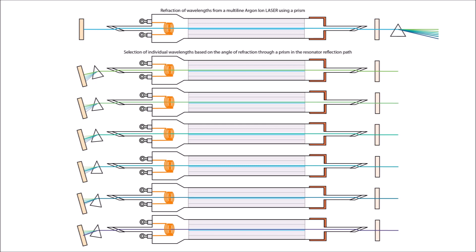Many argon ion lasers are multiline, meaning they produce more than one wavelength of light that can be refracted through a prism as seen in the top illustration. This concept is what allows a single line to be selected when a prism is put into the path of the laser beam between the high reflector and the laser tube. The angle of refraction determines which line produces stimulated emission.